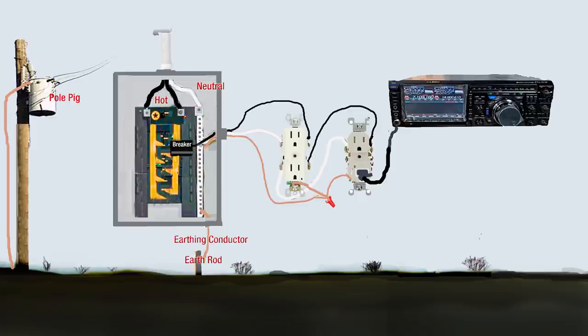The ham radio equipment, then, is plugged into one of those outlets, and the ground pin on the power supply then makes contact and provides a ground. For a lot of folks, adding another grounding rod and grounding conductor to the equipment is a good idea. In my read of the National Electric Code, that is a violation. Again, like it says in the Motorola book, everything should be tied back to one point in the main panel, and not another ground rod that could be either above or below ground voltage.